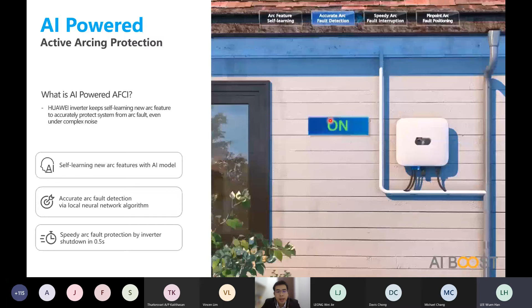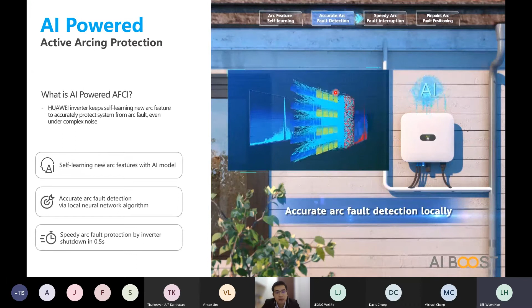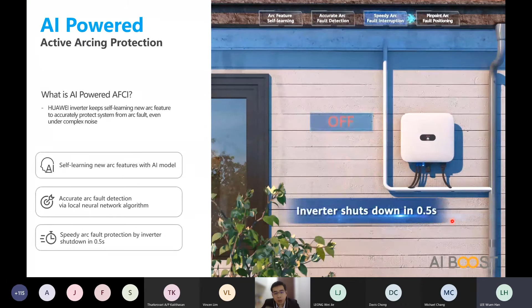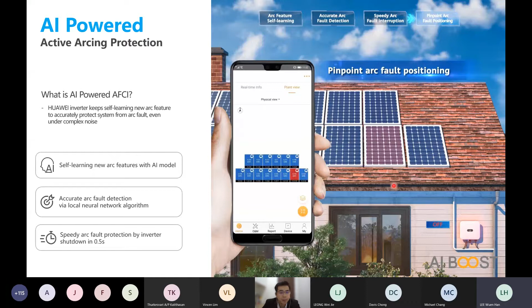And then our inverter has this AI technology to filter whether it's an actual arc fault or interference and so on and so forth. It will filter all this, and this happens in milliseconds. So when an arc fault is detected, the inverter will be turned off within 0.5 seconds. What differentiates us from our competitors is that our AI AFCI has a very high detection accuracy, so false tripping can be avoided. Once it's turned off, the signal will be sent to the user, and you can pinpoint where the arc fault happens with the use of the optimizer. Without the optimizer, you can detect it at the string level.